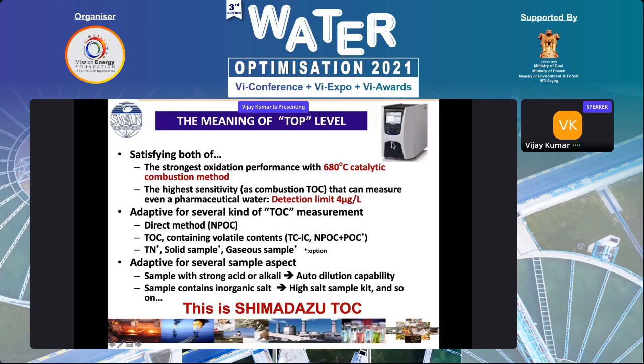We have been dealing with this product for 27 years in India, with a Shimadzu Japanese brand, and supplied thousands of these instruments for various applications. For the past 2-3 years, we started supplying to power plants. NTPC, we supplied many plants. We have a high sensitivity of 4 ppb, and we can measure up to a highest range of 30,000 ppm. We have a TN option, solid sample option, gaseous sample option, and strong acid, alkali or strong salt samples, even seawater and brackish water we can analyze directly.